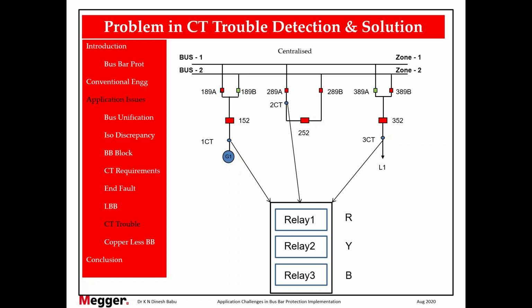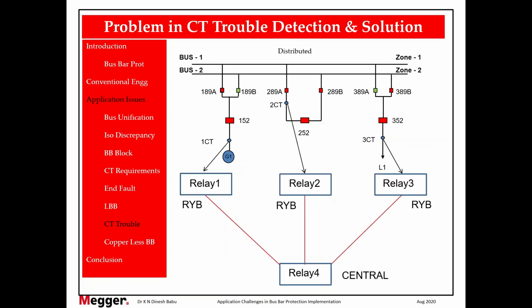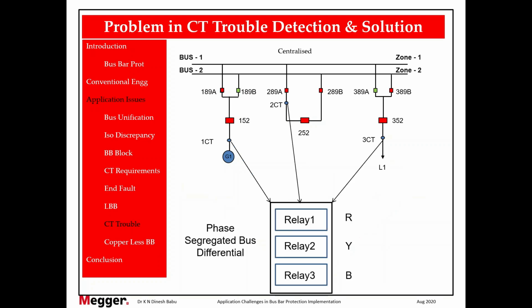For this, we have to understand two scenarios. The centralized bus differential architecture and the distributed architecture. So now we can see the centralized bus differential architecture as shown here. We call this phase segregated bus differential, where each phase from each CT is connected to a separate relay. Relay 1 for R phase, relay 2 for Y phase, and relay 3 for B phase.